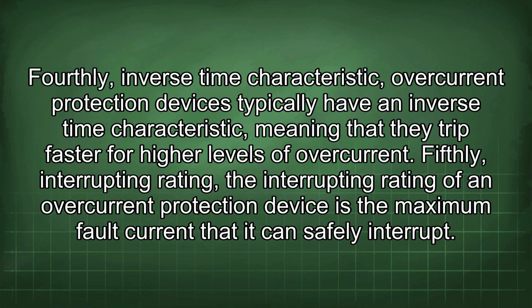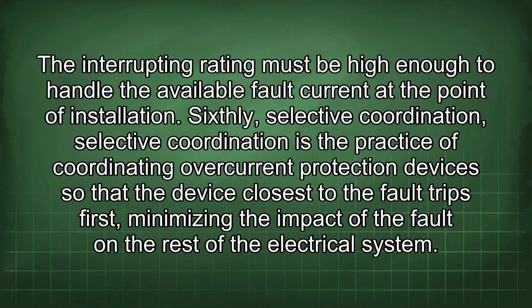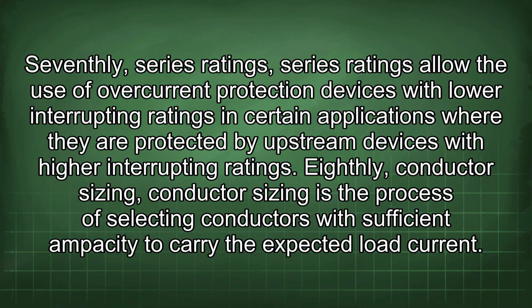Fifthly, interrupting rating. The interrupting rating of an overcurrent protection device is the maximum fault current that it can safely interrupt. The interrupting rating must be high enough to handle the available fault current at the point of installation. Sixthly, selective coordination. Selective coordination is the practice of coordinating overcurrent protection devices so that the device closest to the fault trips first, minimizing the impact of the fault on the rest of the electrical system. Seventhly, series ratings. Series ratings allow the use of overcurrent protection devices with lower interrupting ratings in certain applications where they are protected by upstream devices with higher interrupting ratings.